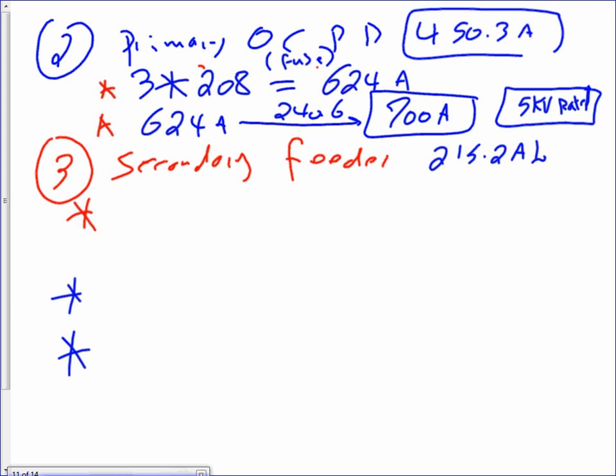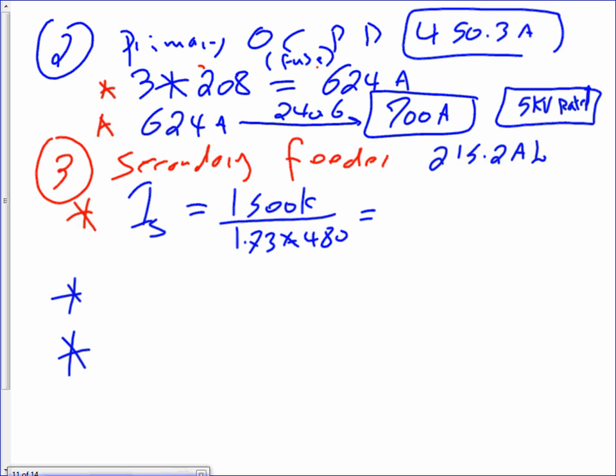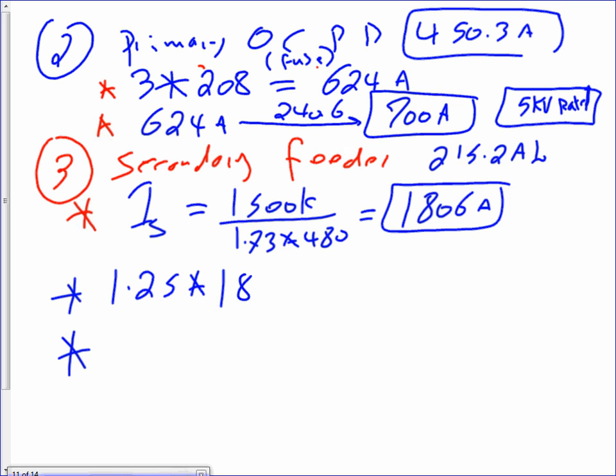Okay, moving into the secondary side, guys. Secondary, piece of cake: you take the 1500 K divided by 1.73 times 480, and it will get you 1806 amps, if you do your math on this. We're going to assume it's continuous load. Again, big assumption. 1.25 multiplied by 1806 will get you a healthy 2258 amps.